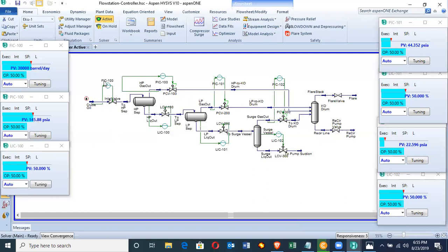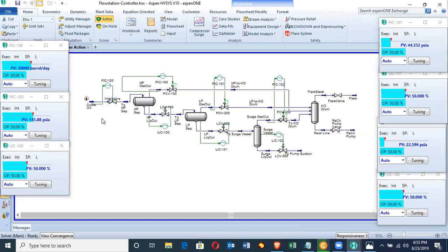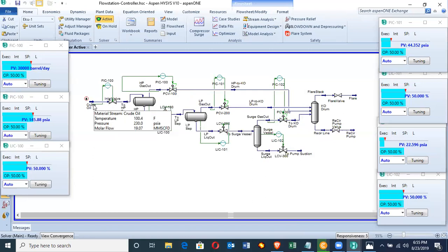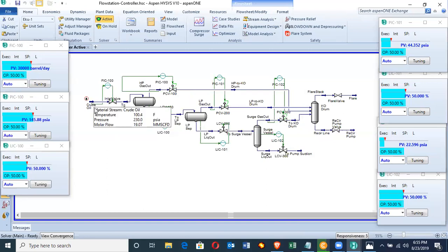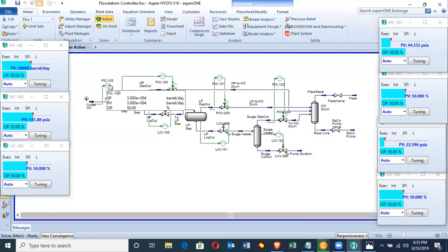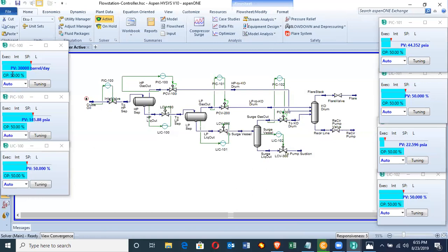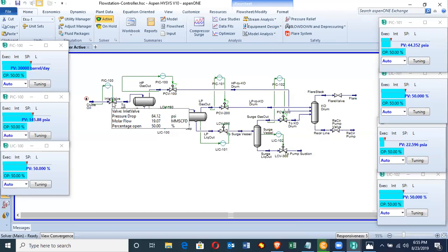For instance, we have a flow indicator controller which is set at 30,000 barrels. It measures the flow upstream of the valve. If the flow is bigger than 30,000 or less than 30,000 barrels, the difference, which is an error, sends the appropriate signal to the valve to either open above 50% or reduce below 50%.